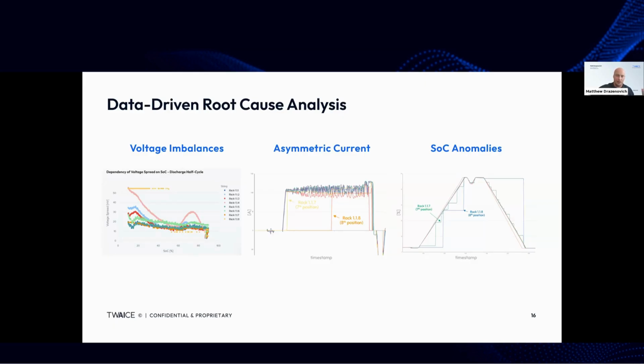Voltage imbalances are often a huge one that we can tie capacity loss back to. In this case, you see one rack having a much larger voltage imbalance relative to all the other racks. Depending on the architecture, that can actually limit the entire capacity of all racks connected in parallel.